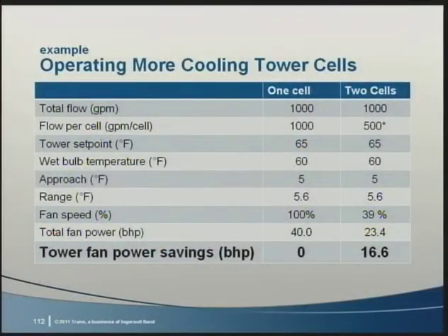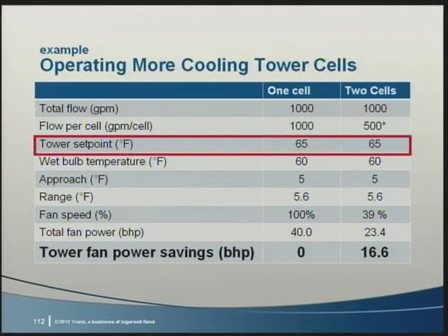Cooling tower performance is shown here. The first column is the operation with a single cell. To achieve the 65-degree set point, at this point in time, a single fan needs to operate at full speed, and that consumes 40 horsepower. If the same water flow is sent over 2 cells, there's more heat exchange surface available. To achieve the same tower set point, the tower fans can be slowed to 39% of their design speed. And combined, they use 16.6 less horsepower than operating the single cell.